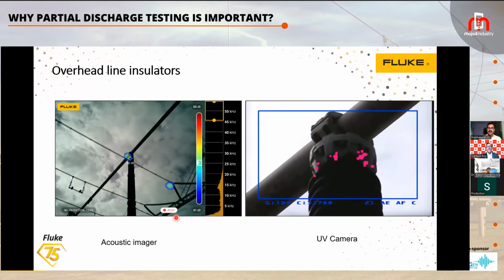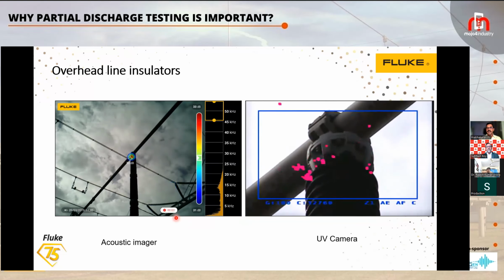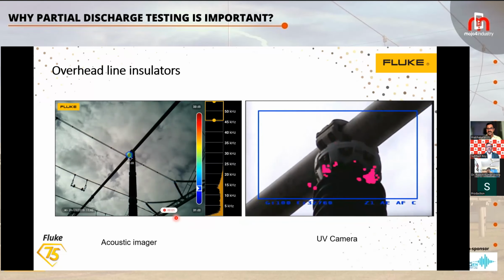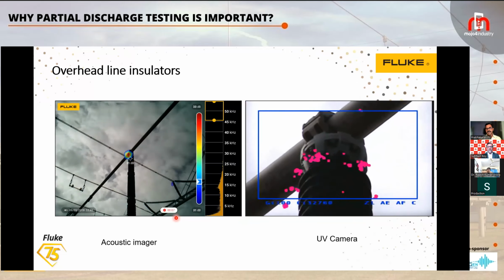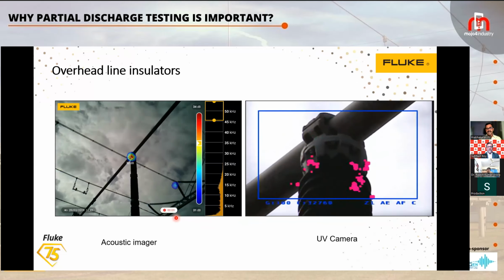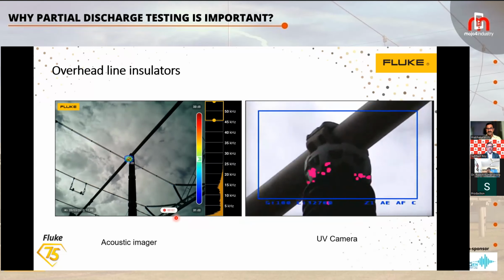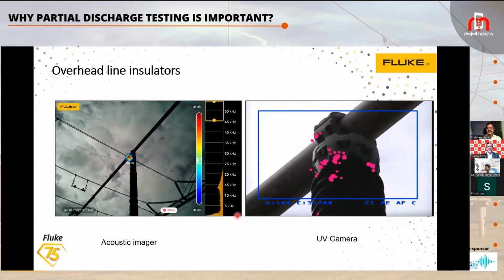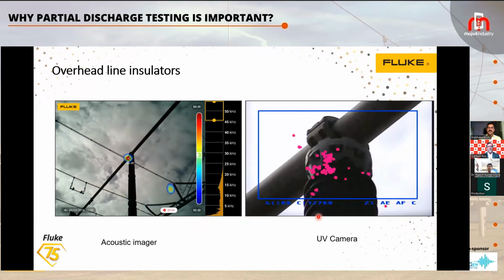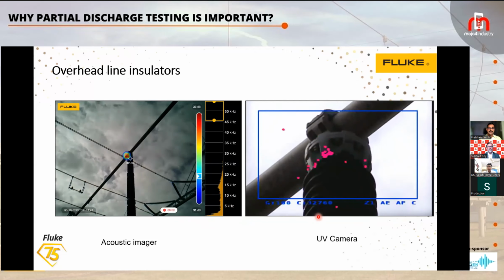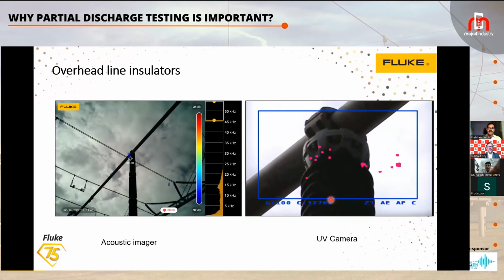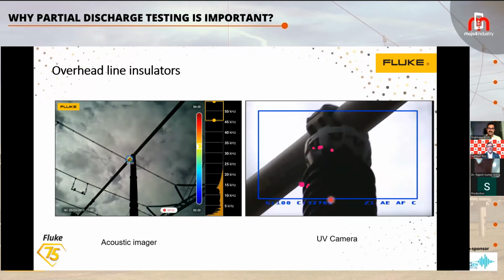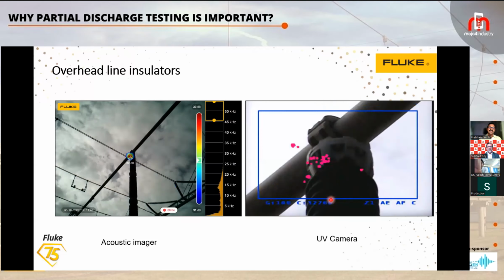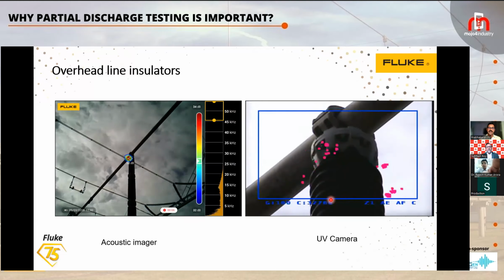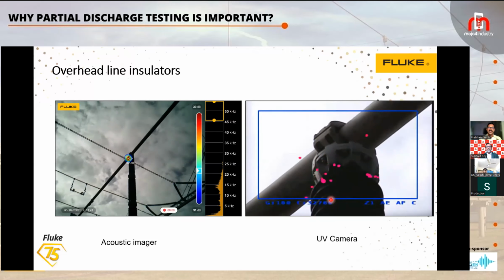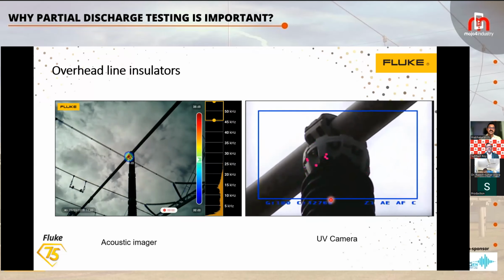Similarly, you also have acoustic imagers and UV cameras, the ultraviolet detectors. Usually ultraviolet detectors are used for corona detection, so they're called corona cameras. There, light has its own challenges, and you get very limited information with these cameras, plus challenges with daylight. But with acoustic, it is easier to use and much richer in the content and information you can get.